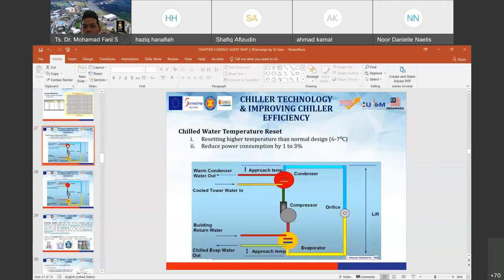Chill water temperature reset. Okay, resetting to a higher temperature than the normal design reduces power consumption by 1 to 3%. So about 6 to 7 for the supply chill water temperature reset.